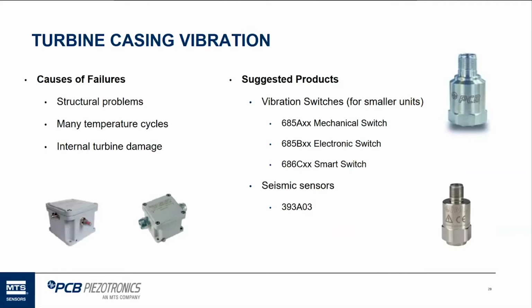It's no power required. It has relay outs. There's different versions and different types of relays we provide inside. Different sensitivities and vibration limits can be set within that. So basically, it shakes and has a relay out that can go to this turbine switch hardware, which controls the turbine, to shut it off if needed.